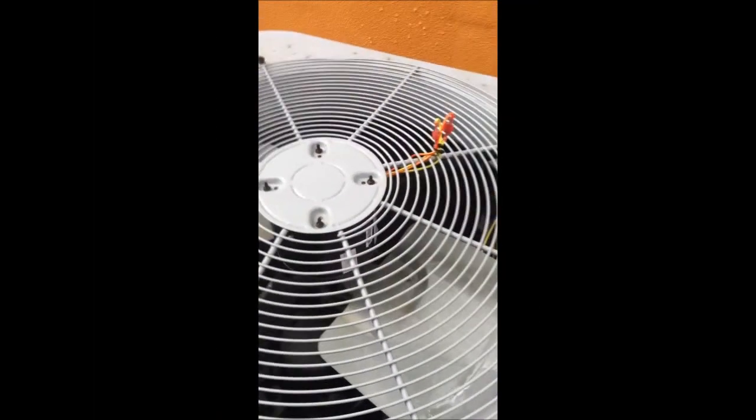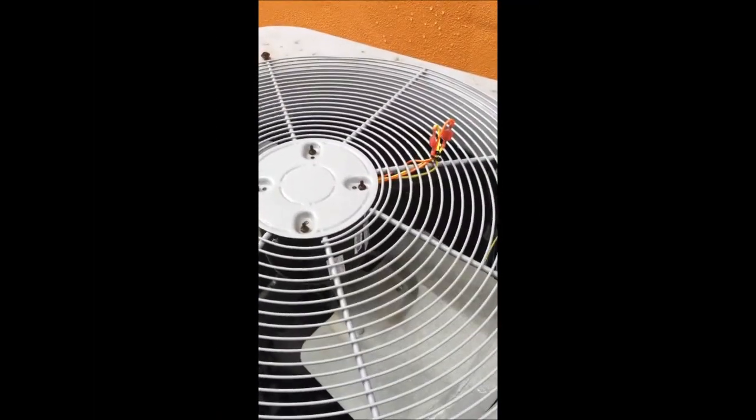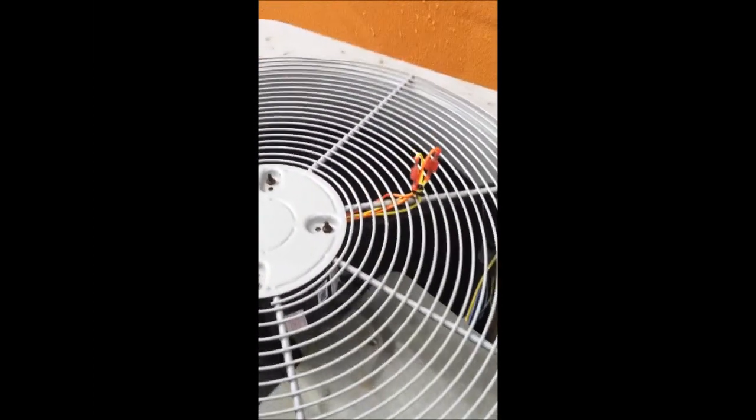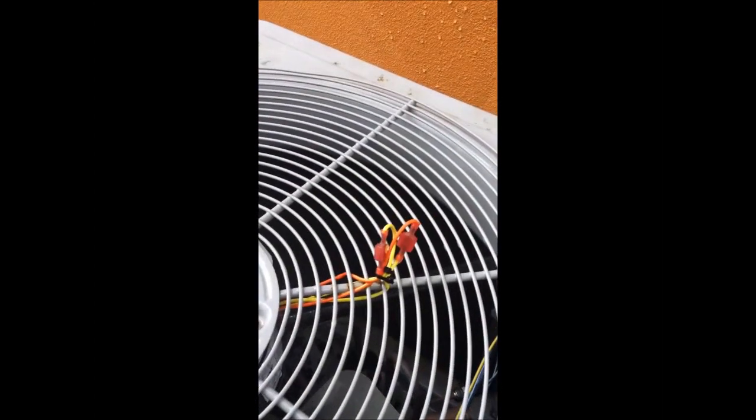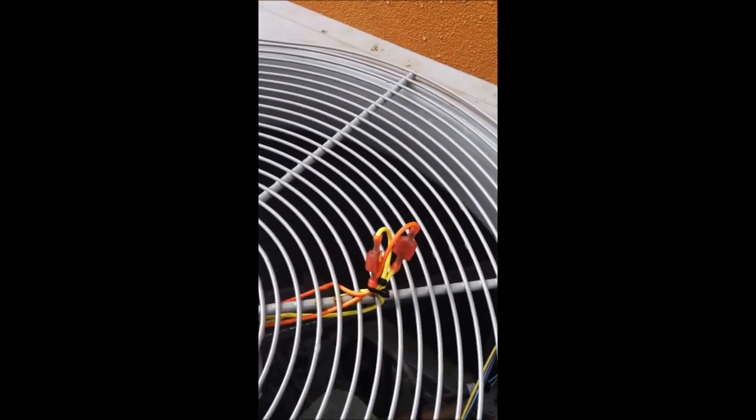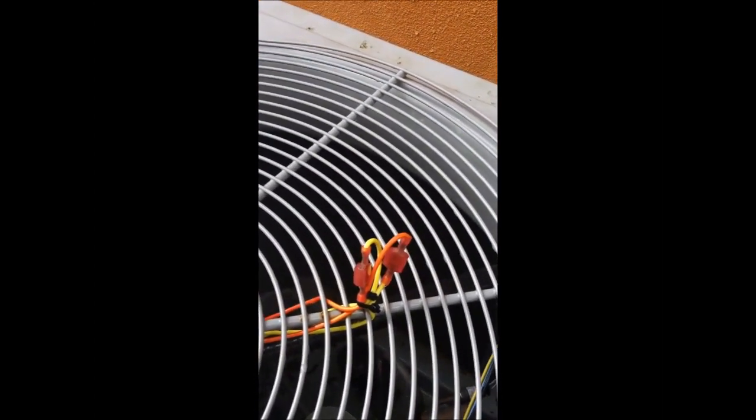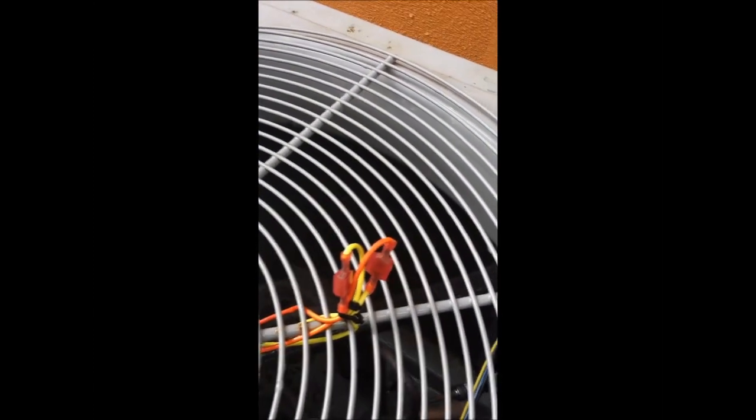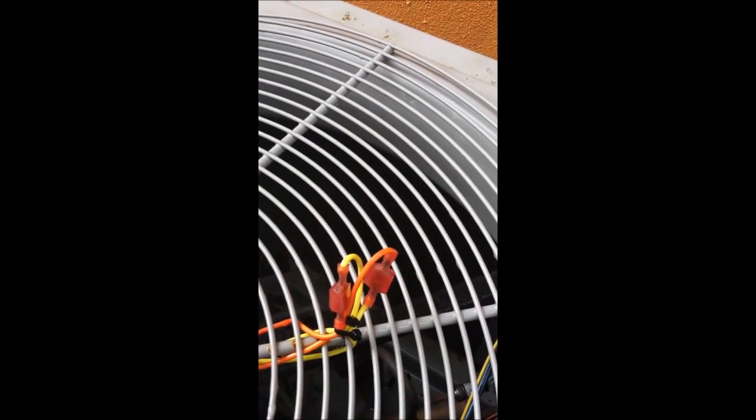All right, so I'm out here taking a look at a recently replaced condenser fan motor and this is a universal replacement. You can tell that because you see these orange and yellow leads. These allow the condensing fan to be switched from clockwise to counterclockwise. This is probably not a great idea to have them hanging out of the top of the condenser fan cage here.